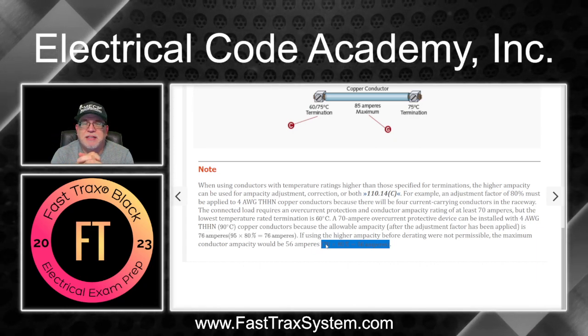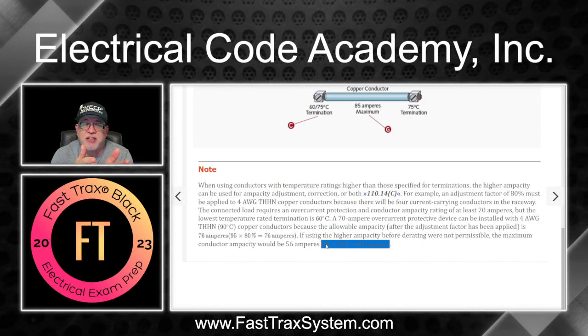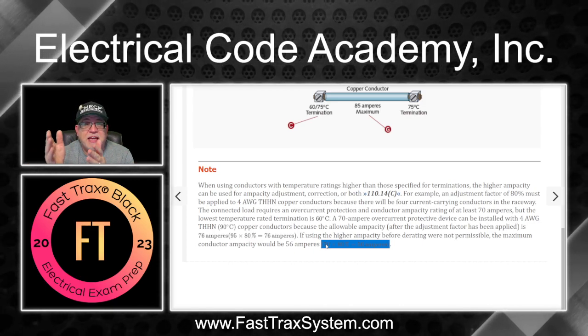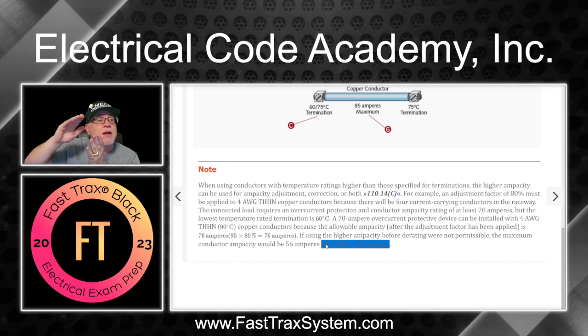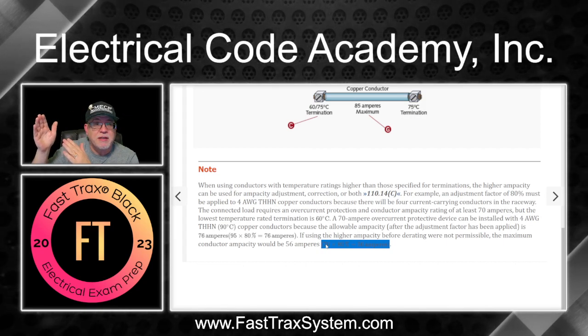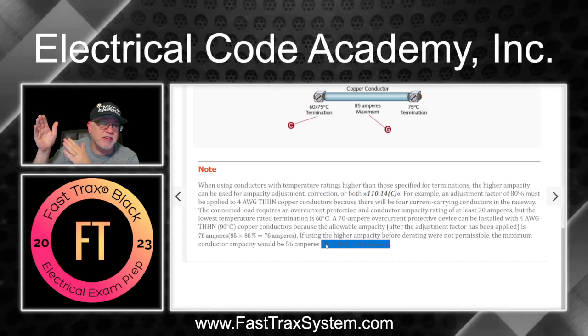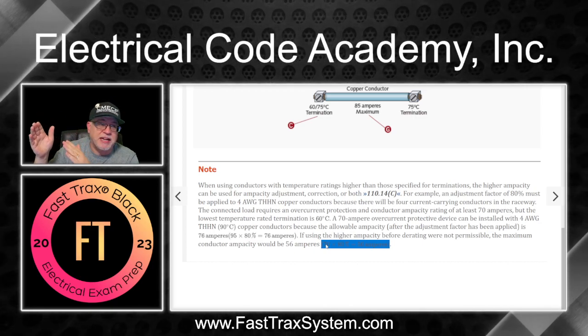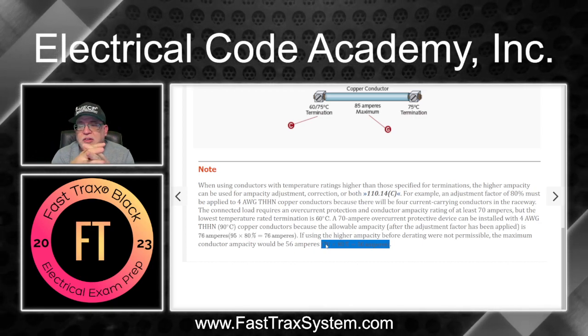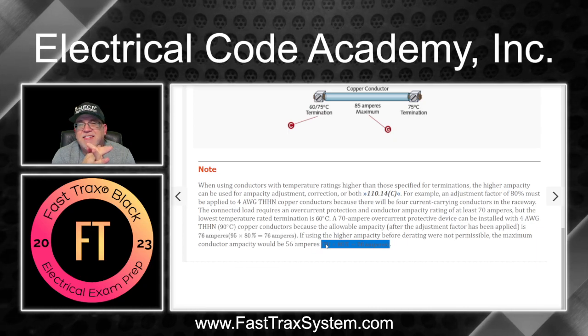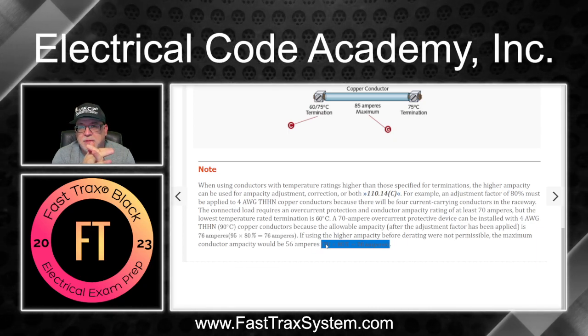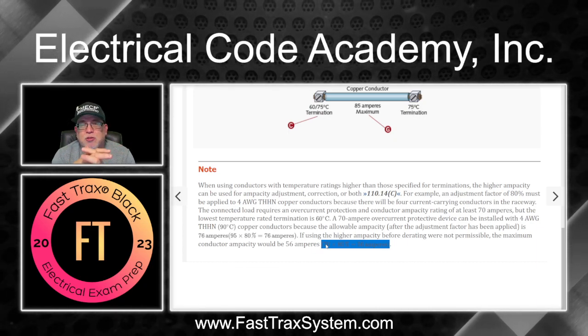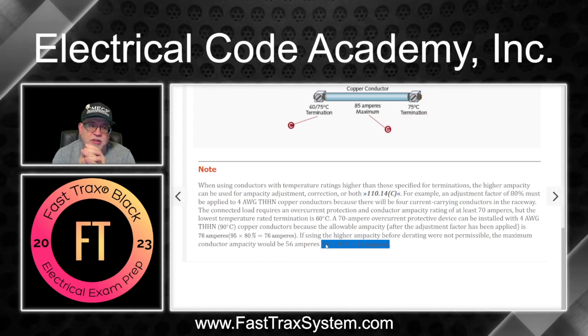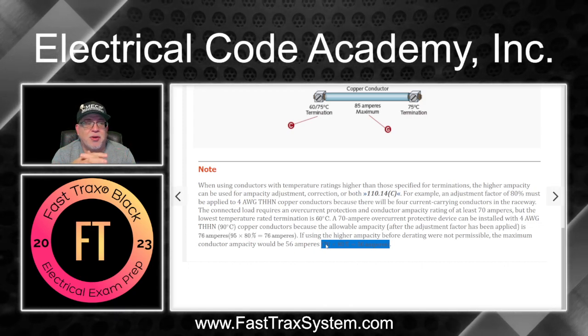334.80 for non-metallic sheathed cable, which is going to limit you to the 60. Even though it's going to do the same thing, it's going to let you use the 90 ampacity because the insulation on those conductors inside of an NM cable is rated for 90. But ultimately, at the end of the day, you still can't exceed the value in the 60-degree column, and you still got to make sure that you can handle the load after an adjustment or correction. If that confuses you, don't worry.